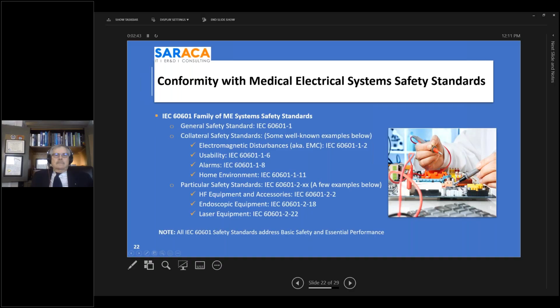So the theme of this is that having your 601 test report doesn't guarantee you meet the 601 standard in its full glory. This is where I will be bringing forward these aspects of 510K submissions that are getting held up and challenged. The FDA has taken a harder stance in this area and has bolstered its expertise and understanding of what the standards are asking for. The reason is that there have been class 1 recalls occurring, and these test houses aren't challenging the products enough. They don't know how to challenge essential performance. Basic safety has always been in their back pocket over the years, but essential performance is where people struggle more.